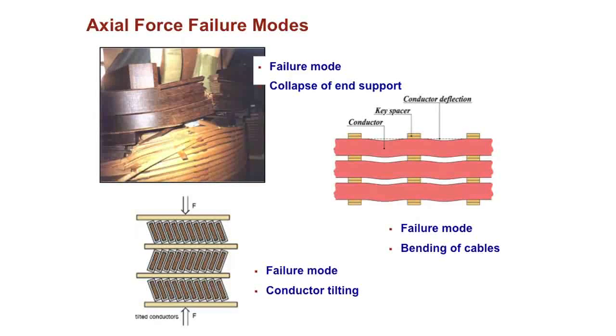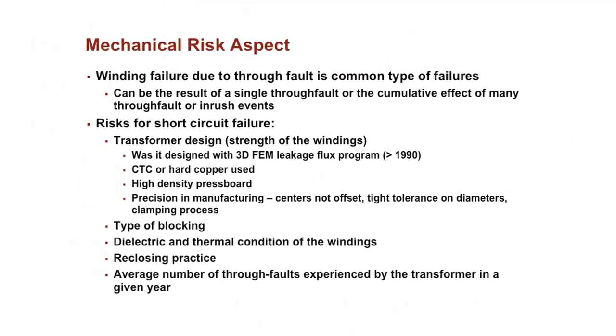So usually what will frequently happen is the integrity at the end of the windings will be compromised, and you'll get lots of damage at the end of the windings, and then if it's enough, the winding will just come right apart. So when we look at a short circuit failure, we first look at the transformer design.